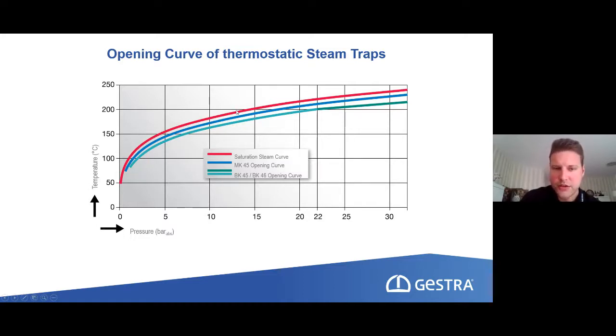And then in the end, we have a curve here in the beginning at lower pressures. And if we go to higher pressures, we go into, let's say, a straight line. The curve is only at low pressures. So why do I tell you that? Because I want to show you the two lines below the red one. These are the opening characteristics of the two thermostatic steam traps: the MK, which is the blue one, and the BK, the bimetallic one, which is this green one.